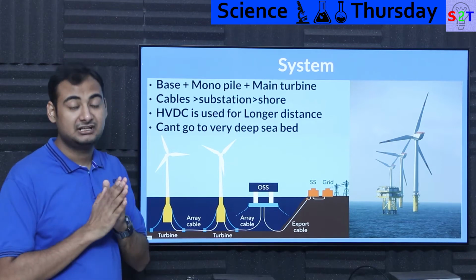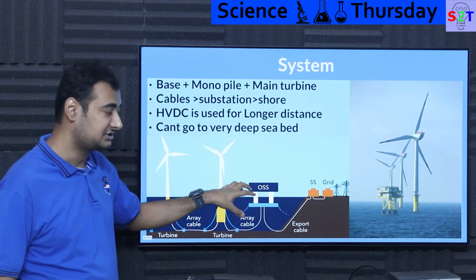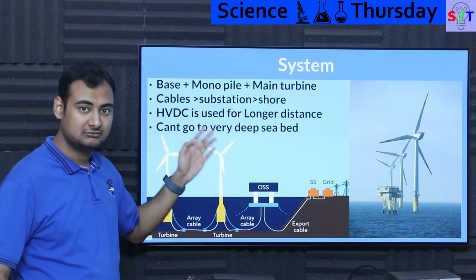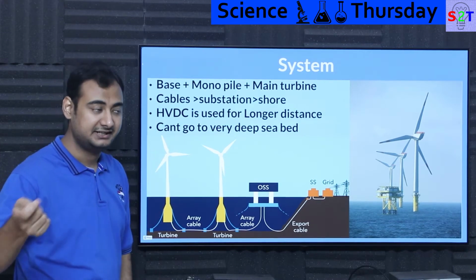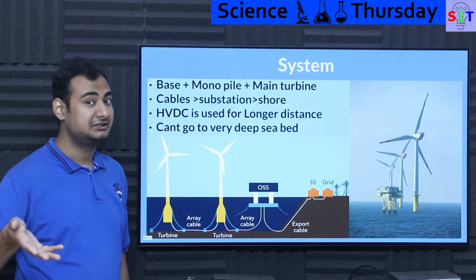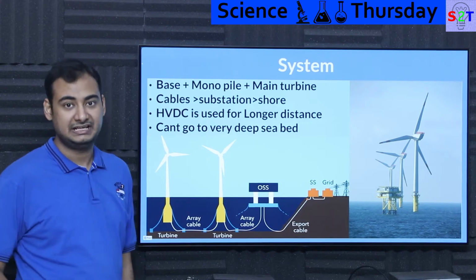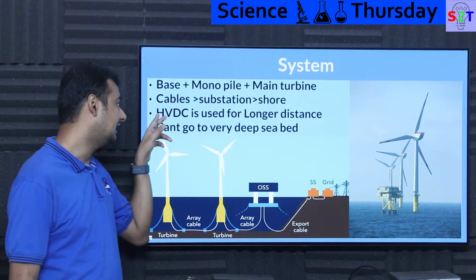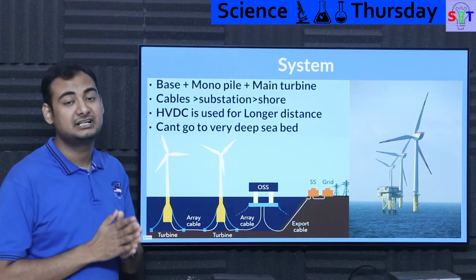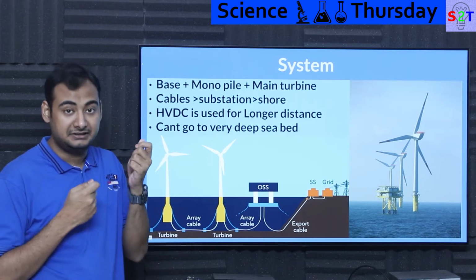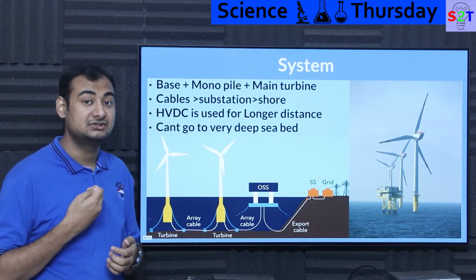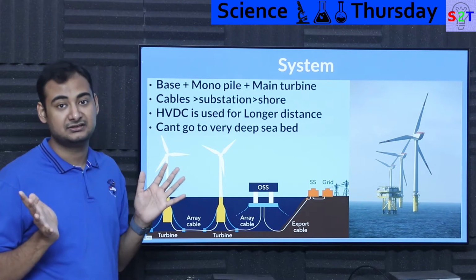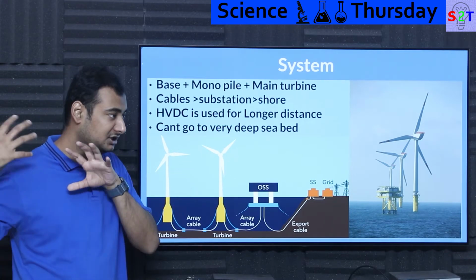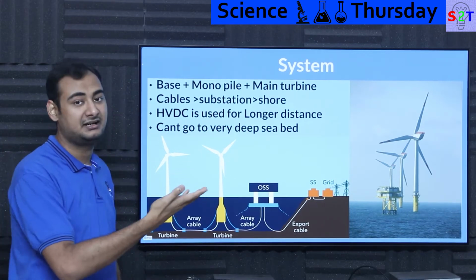Now be mindful, if the land is very far away — basically the distance between the substation on the sea floor versus the substation on the land side — if it's 50 kilometers plus, they're never going to use AC. They'll use what we call high voltage DC. The primary reason is that the higher the distance under sea water, the capacitance loss is too high. You'll lose most of the energy just transmitting it. So you could have a 1 gigawatt farm and barely send anything.